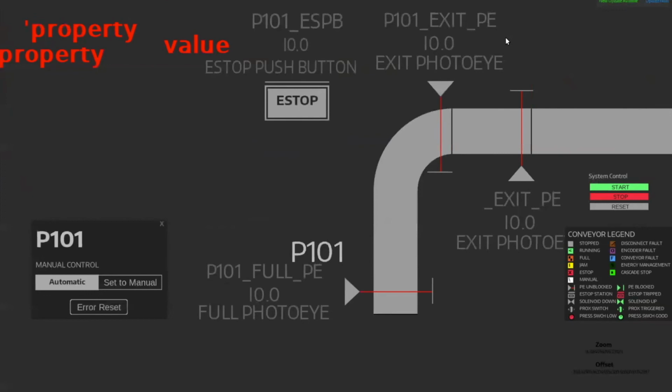But if everything is standard, then at this point, once you set the IP address, once you have the code inserted in the status array, the code inserted into the HMI code table, then when that conveyor is turned to running, this will turn green. There's nothing else you have to do. Everything should be linked. So yeah, that's kind of the basics of setting up graphics.